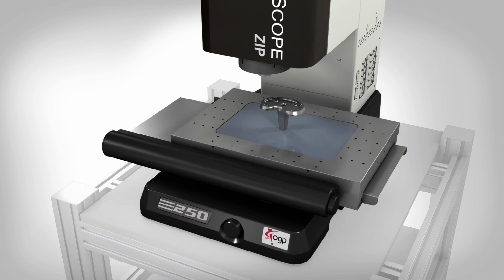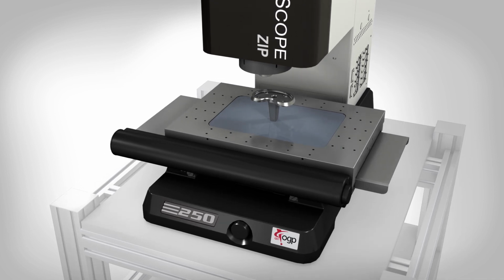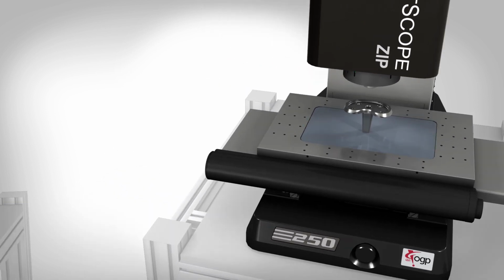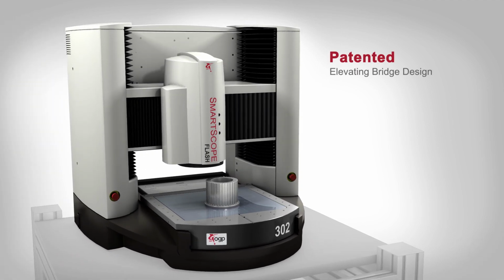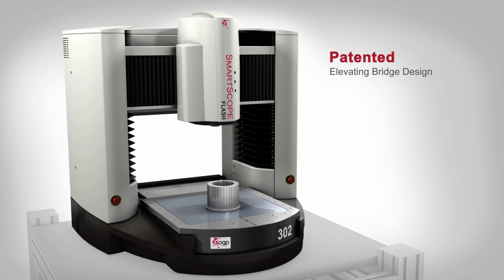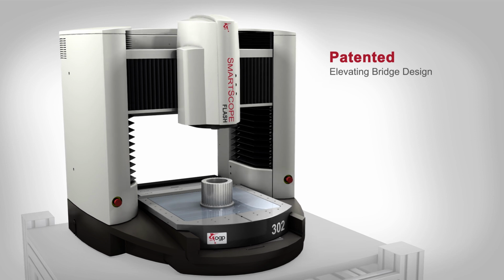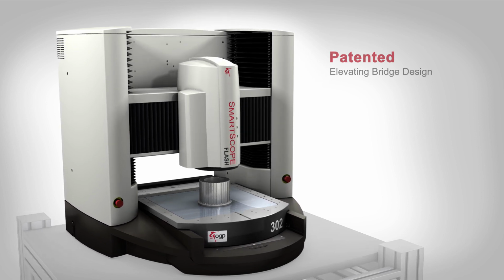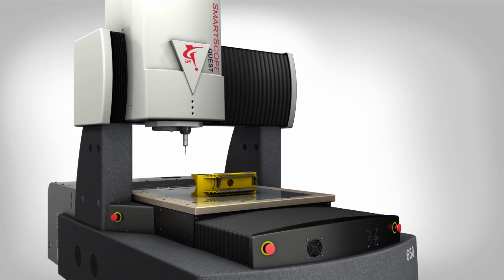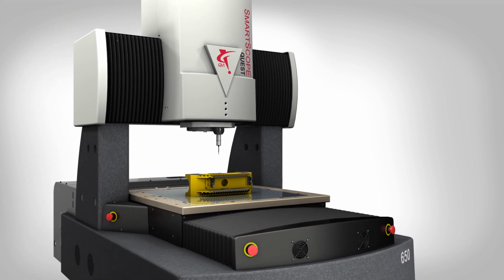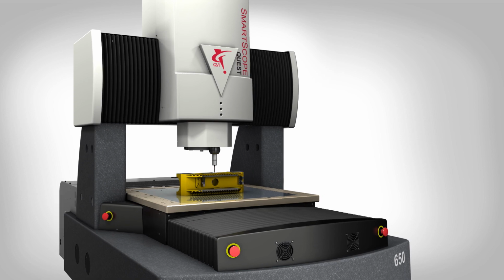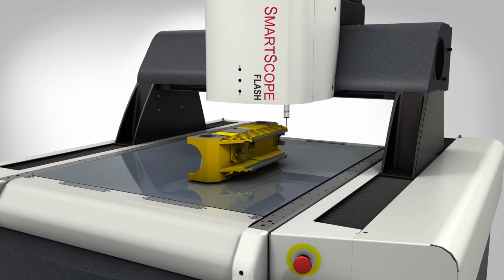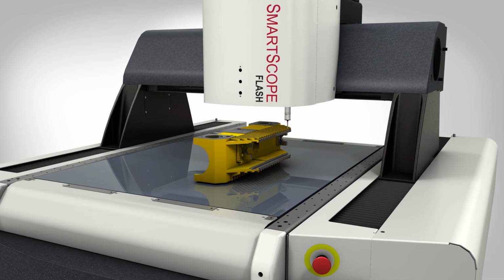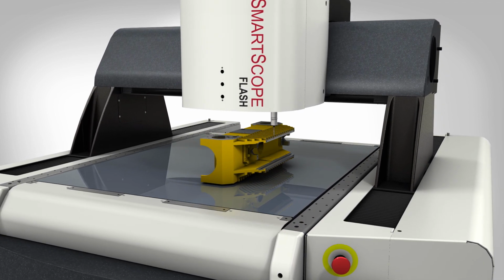Compound stages are designed to measure smaller parts or to be used where space is at a premium. The patented elevating bridge design of SmartScope benchtop systems makes efficient use of space while enhancing accuracy through designed-in mechanical integrity. Floor model systems feature fixed granite bridges that separate the axis motions for advanced accuracy. The largest SmartScope systems offer a moving bridge, allowing the optics and sensors to move around large, heavy parts.